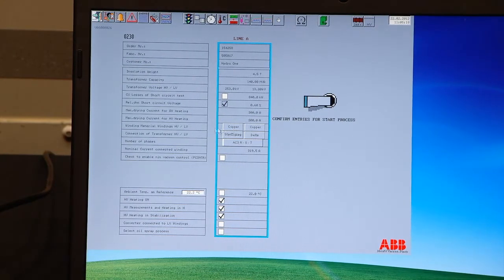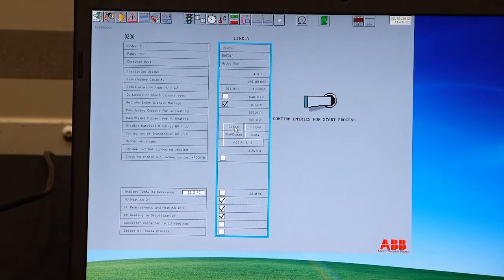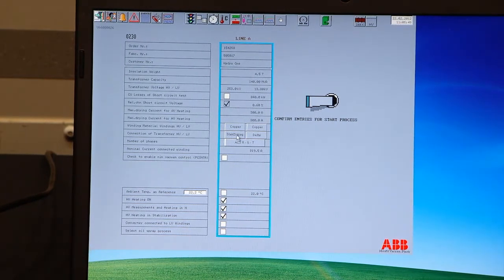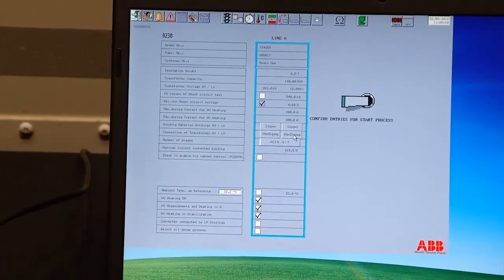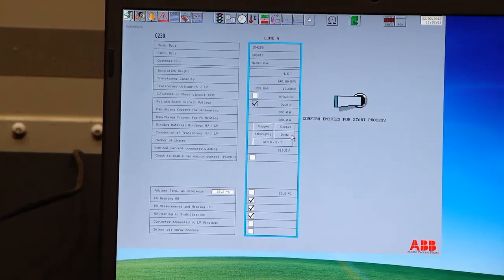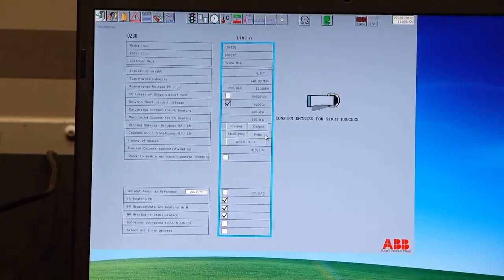Important is to select the winding material, if it's copper or aluminum. Normally you're always working with copper, but you will have aluminum cases. If this is wrong, you will have a wrong temperature calculation in the heating up. You're coming to the transformer connection. You have 2 options, either star and zigzag, or delta. You simply click on it and it changes. And this is for the high voltage side and also for the low voltage side. Do the same. Also information from the transformer data sheet.